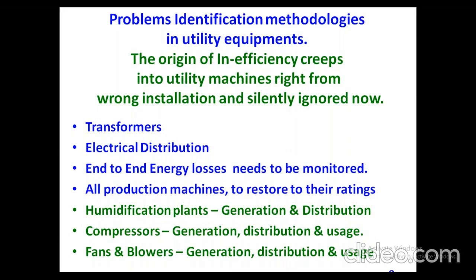Especially with many of the production machines that are bought, the management takes utmost care. If it is an auto corner, they will go for a 250 kVA UPS, and many of the machines get all the protections, whether it's a constant voltage stabilizer or a servo stabilizer for an auto corner or a carding machine. They do everything. But when it comes to the utility, they say, okay, whatever is given by the OEM, let us do it. If there is a mistake at the time of installation, the inefficiency creeps into all the utility machines right from the installation, and that is silently ignored by the industry.